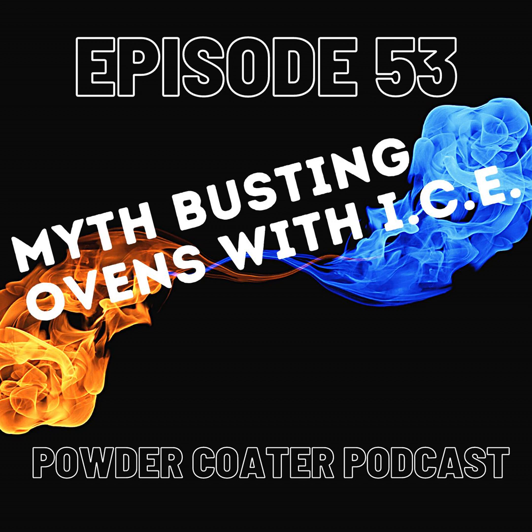Okay. That makes sense. And when you compare electric or natural gas to propane, the heat coefficient of propane is about 2.5 times what natural gas is. In other words, 1 cubic foot of natural gas is typically about 1,000 BTU, depending how they mix it at the supplier. Propane on average runs about 2,500 BTU per cubic foot. Okay. So when you start looking at the numbers, there is an offset, because you're getting a higher heat coefficient, so it gets a little bit closer to natural gas, even though it's more expensive, but natural gas is still the best way to go.